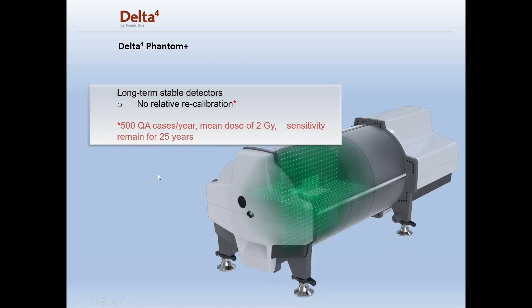The Delta IV Phantom Plus is a digital phantom, very stable, using diodes. These are long-term, stable detectors. There is no relative calibration needed, and they stay incredibly stable over the course of their life.